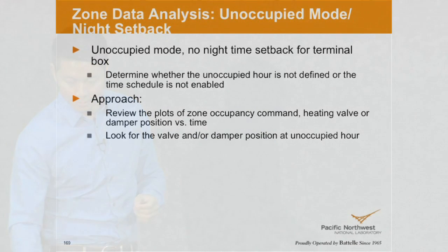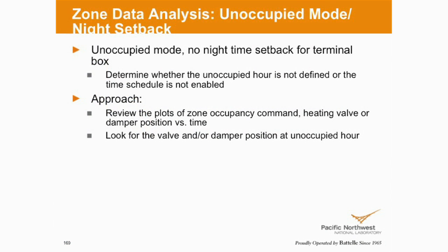So what's your normal setup for the band? 4 degrees? Okay. Yeah, our simulation shows that by widening that range, the savings are significant just by changing that cooling and heating set point. We want to look at the unoccupied mode, to see if there's a setback or not during the unoccupied hours. So we review the plots of the zone occupancy command, the heating valve position, and the damper position over time.